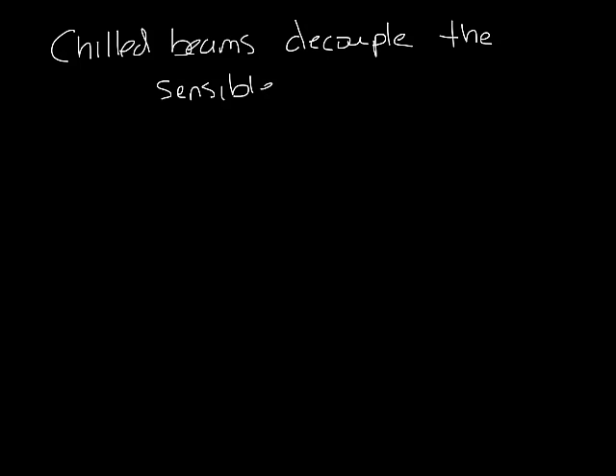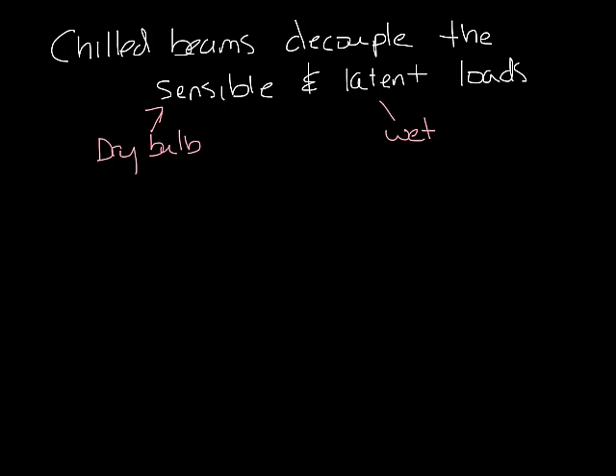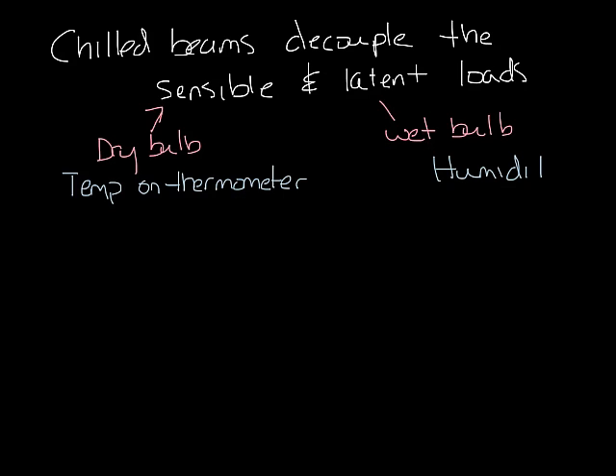Chilled beams decouple the sensible and latent loads in a space. You can probably find a dozen good explanations for sensible and latent load online. The Engineering Toolbox defines it as the sensible cooling load refers to the dry bulb temperature of the building, and the latent cooling load refers to the wet bulb temperature of the building. Think of sensible load referring to the temperature on a thermometer, and latent load referring to the humidity.